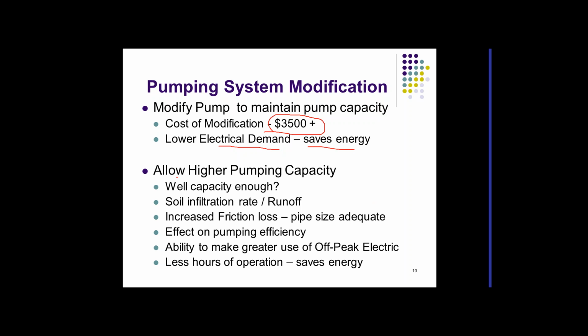The other option is to allow the pump to run at a higher capacity. So let it run at 1,100 gallons a minute. What we have to make sure is that the well has enough capacity to supply the water to the pump, and that the infiltration rate or runoff is not an issue. The trade-off here is it makes us more drought resistant because I can put the water on faster.